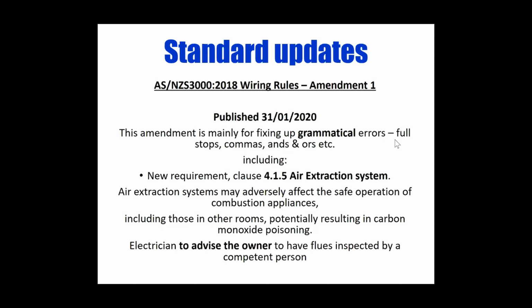The only real thing that actually has been added in that amendment is clause 4.1.5, air extraction system. Now that's anything that extracts air from your household or factory or whatever. So let's talk about just a bathroom exhaust fan or a range hood above a cooker. All of these are air extraction systems. Now, what the standard is actually telling you that you have to do is, when you do install an air extraction system, you actually have to make the owner aware that they have to get their flues inspected by a competent gas worker, or the standard says a competent person.